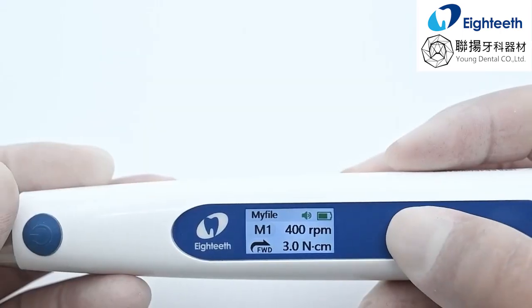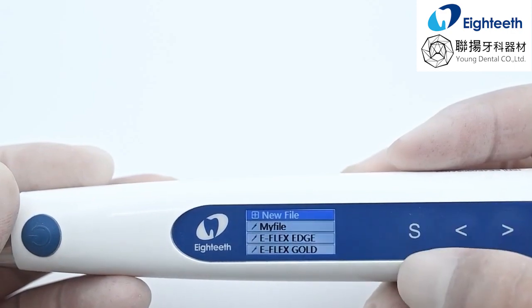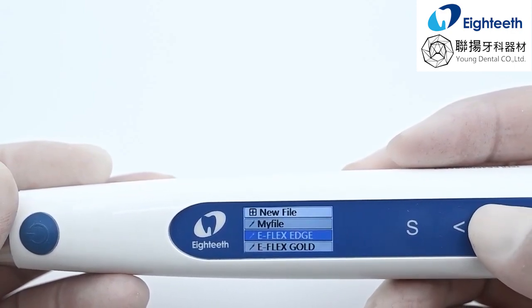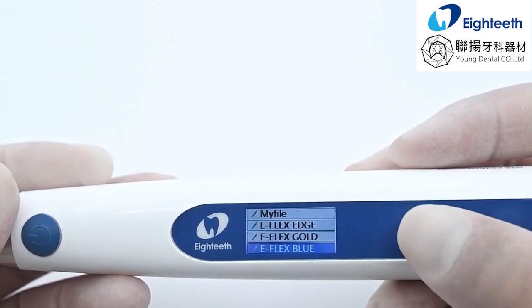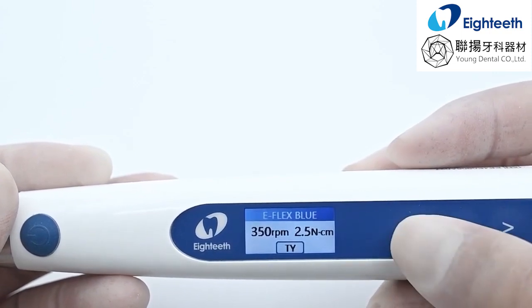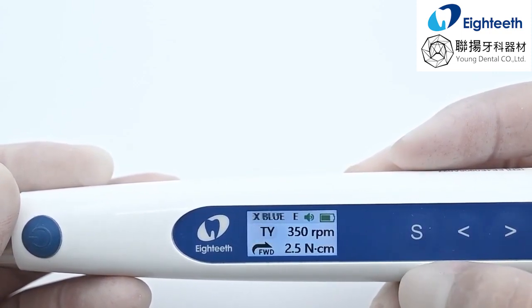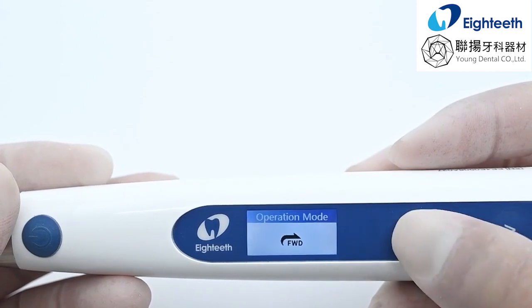In M1 to M10 mode, long press the setting button to select the endo file system. The device will automatically set the rotation speed and torque recommended by the manufacturer. You can also change the speed and torque.